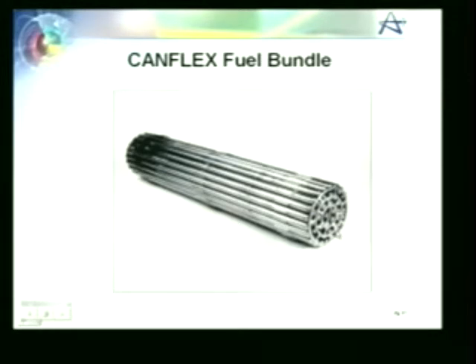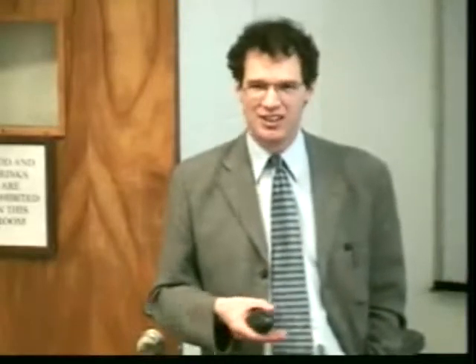The time average bundle power, for physicists, is about 910 kilowatts. The time average channel power, each channel on a time average basis, is 7.3 megawatts. Instantaneous power would be 7.8 megawatts. The CANFlex 43-element bundle has allowed us to go to much lower linear element ratings, from about 63 kilowatts per meter to 51 kilowatts per meter. So from a safety analysis point of view, these are all good things.